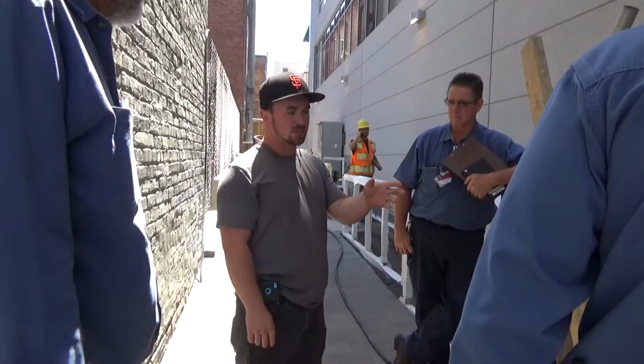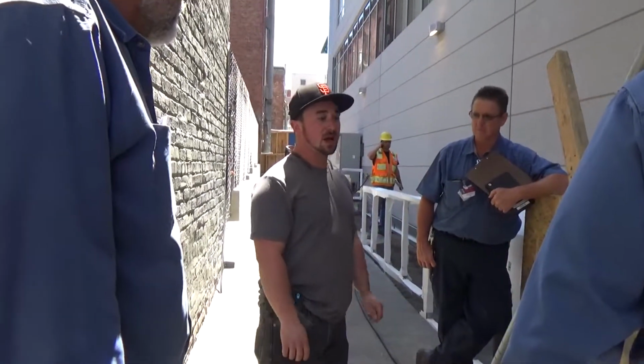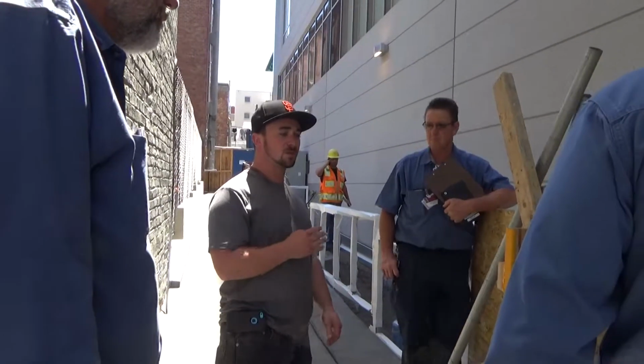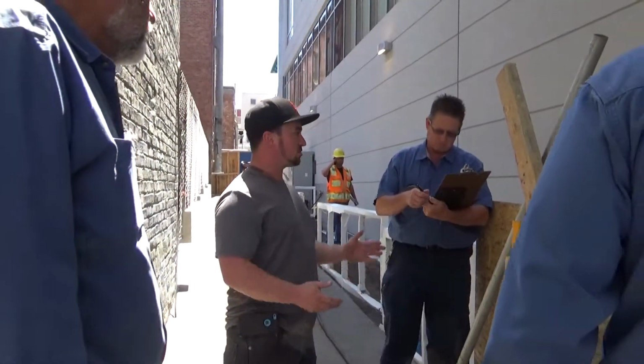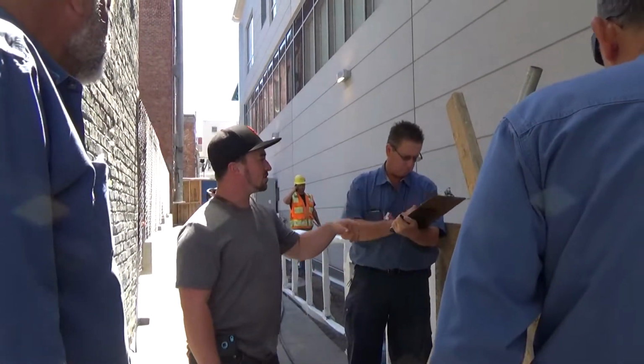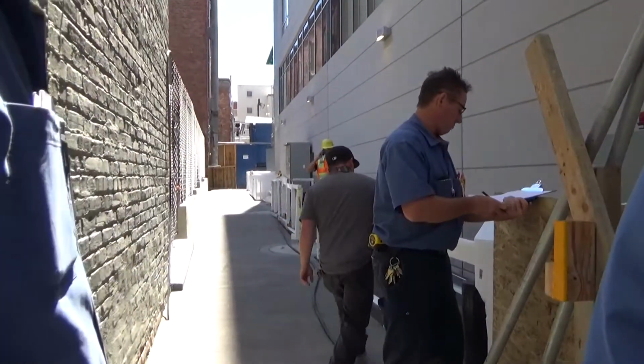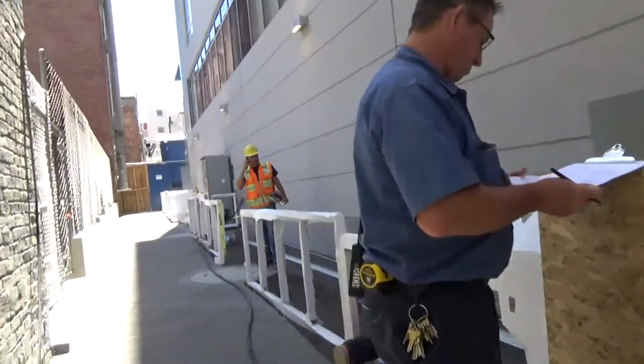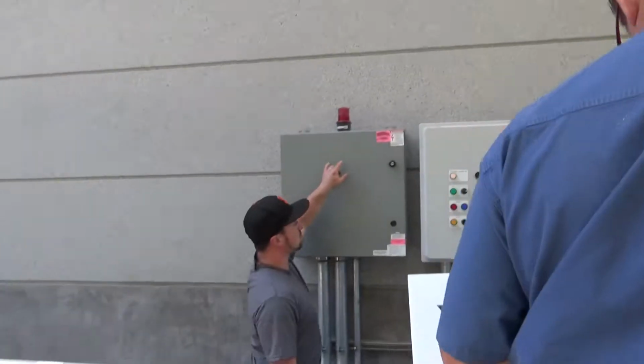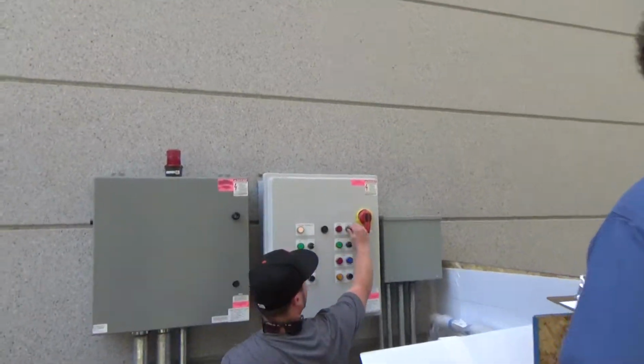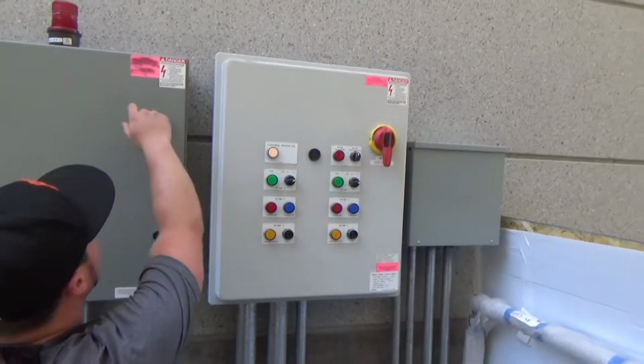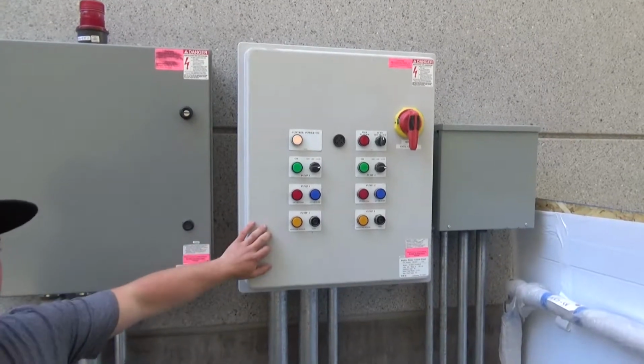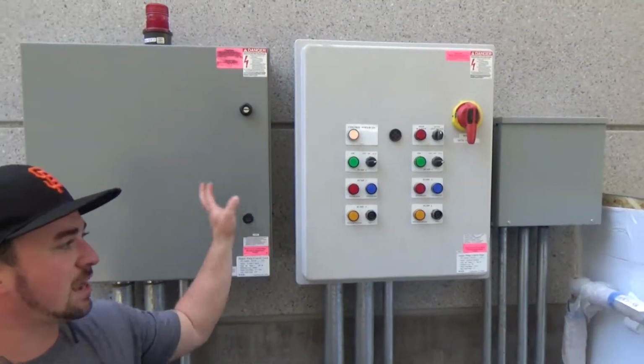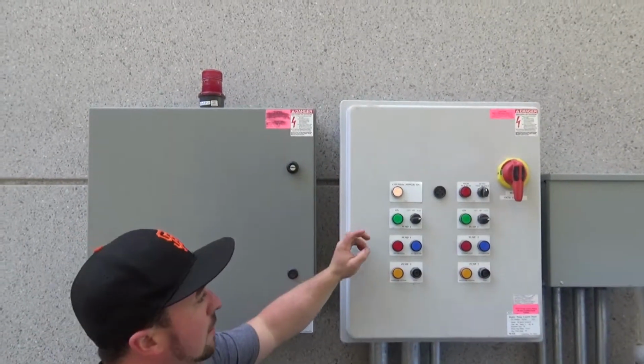So say there's an emergency and it fills all the way up to that high water float, the top float, the 4th float from the bottom. That's your high water, and it's going to give you an alarm. This has a red light on top, so it'll give you a loud buzzer, and it'll flash. This one doesn't have that. For some reason they ordered 2 different types of panels, I don't know why.